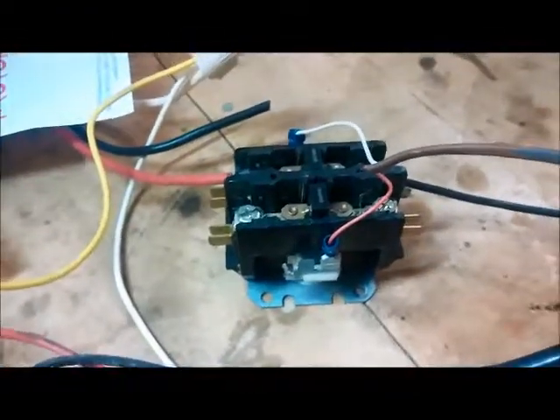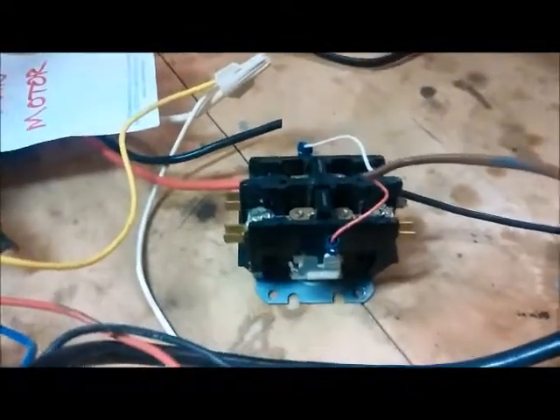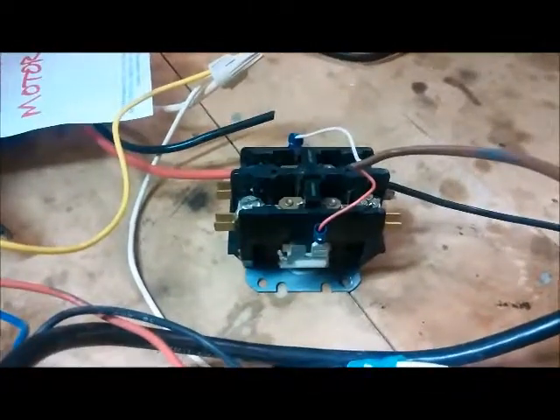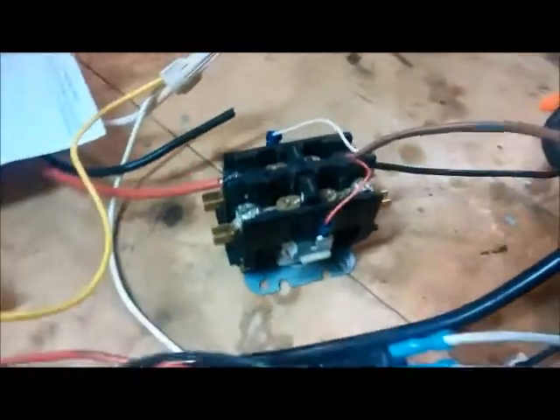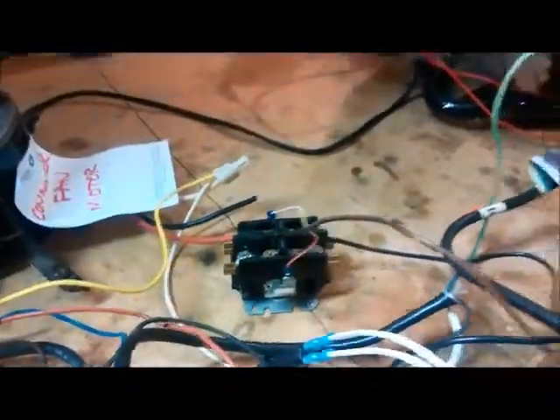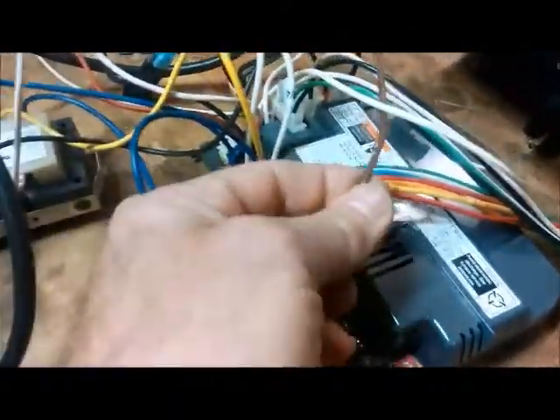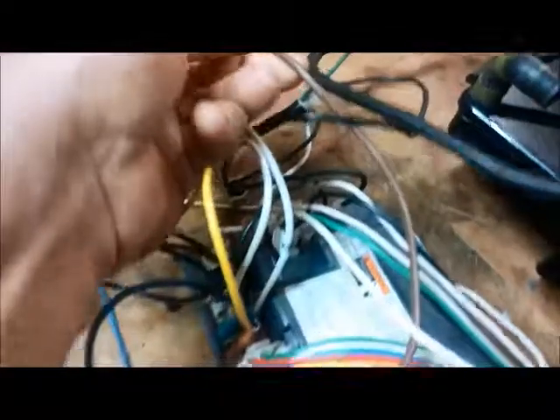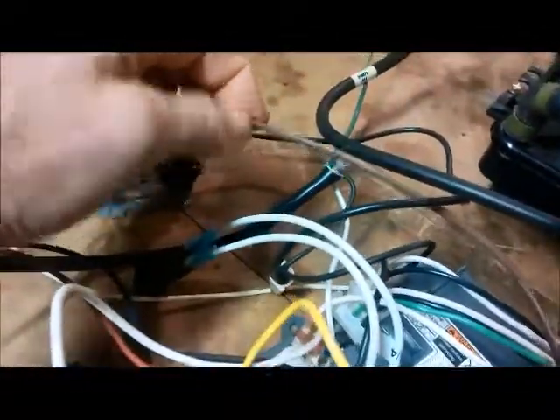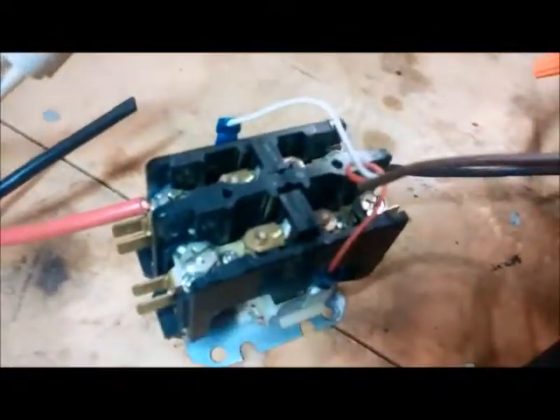I've seen it twice, 3 times in 15 years. But if you don't know to look for that, that can be a real joy to find. If I don't see any obvious frays or shorts, sometimes you've got this wire going out to the air conditioner. The weed whip from the lawn guys is taking the coating off of these, and the red and the white are shorted together. That's a simple one.